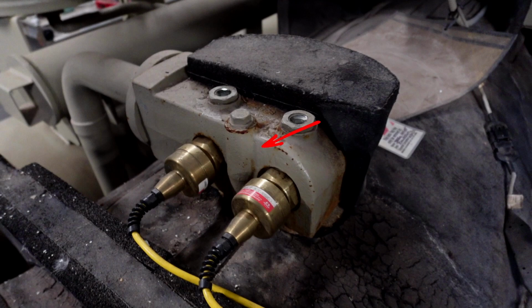There's still a lot of chillers out there that are using fixed plate, or fixed orifice, I should say, metering devices. So with a fixed orifice, they're using literally just a steel plate with a bunch of holes punched in it. Now it's not that haphazard. It is specifically engineered to have a certain flow rate and pressure drop across it, but it's still a fixed bore style of device. Those are still used even in very large applications because it's a very consistent technology that they can design variability into. That's a whole other topic in and of itself.